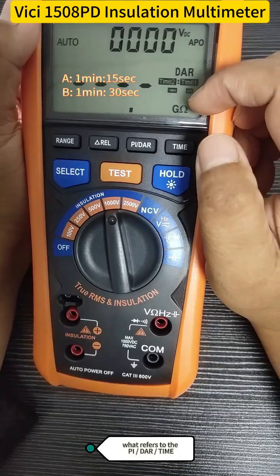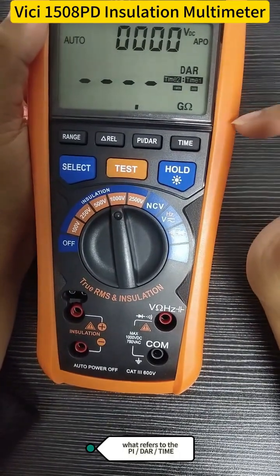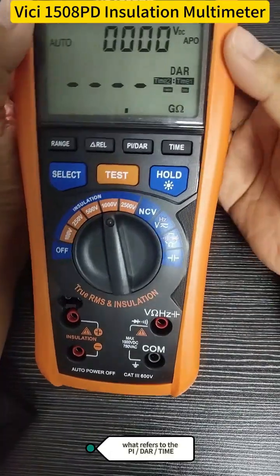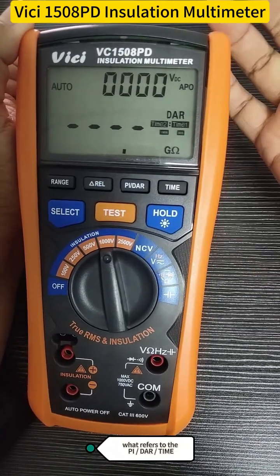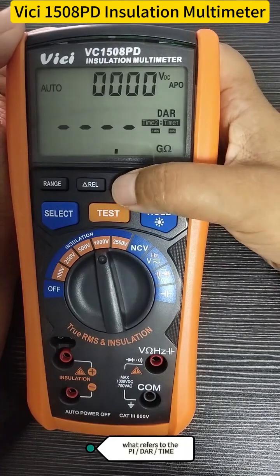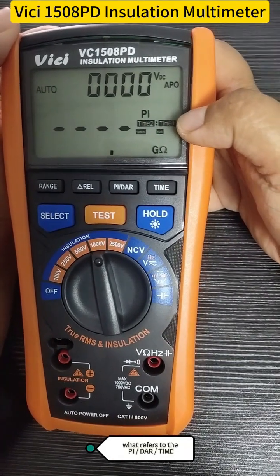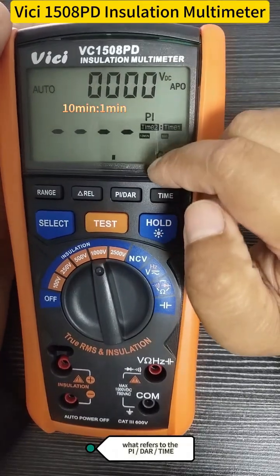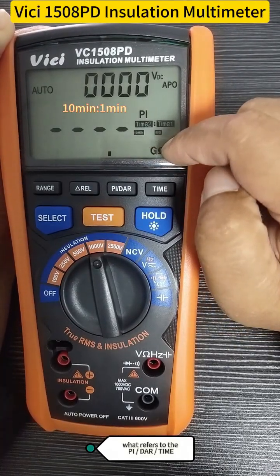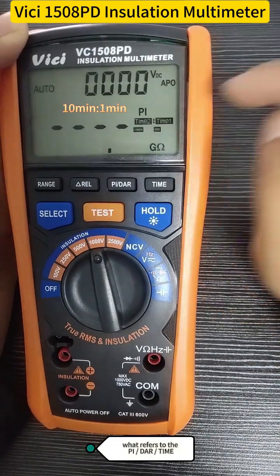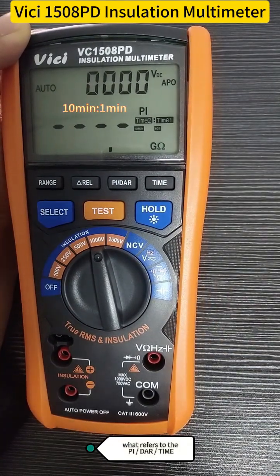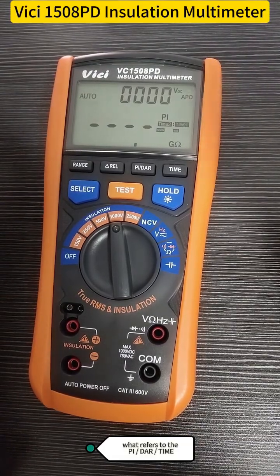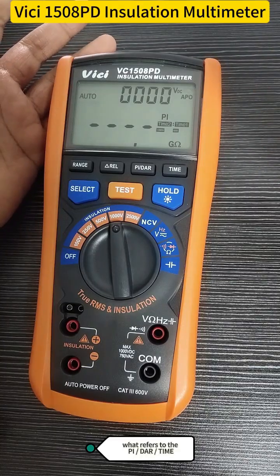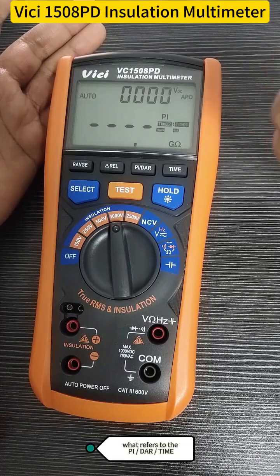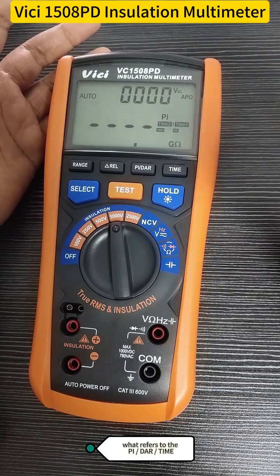A reading above 1.3 is good. If it's lower than 1.3, it might have oil, dust, or partial damage. Try cleaning the equipment and testing again. Next, let's see the PI, the automatic polarization index. It is the ratio between the insulation resistance at 10 minutes and the insulation resistance at 1 minute of the test. The standard pass mark is over 2.0. For motors, transformers, and high voltage cables, a normal single reading doesn't always mean you are in the clear. A lower PI means moisture inside. Powering it on directly could cause a short circuit, so dry it out thoroughly first.